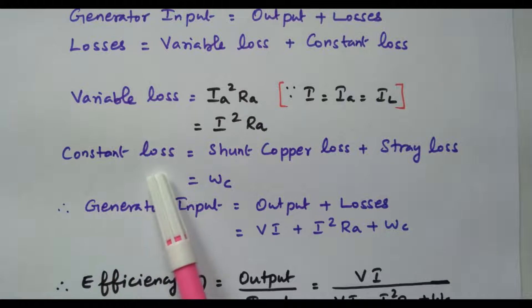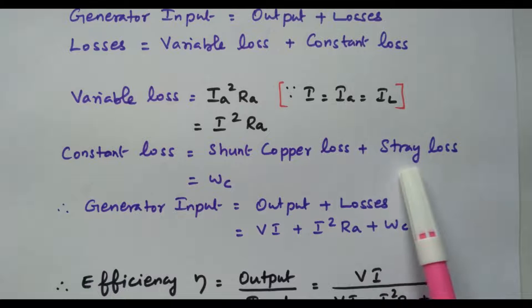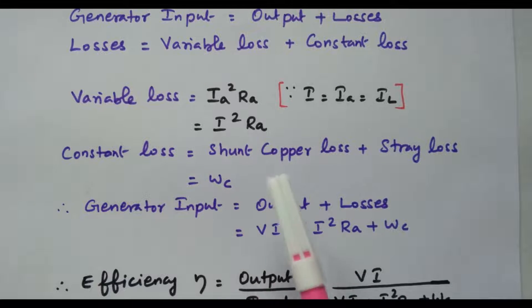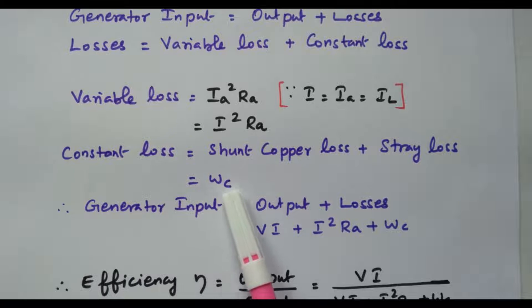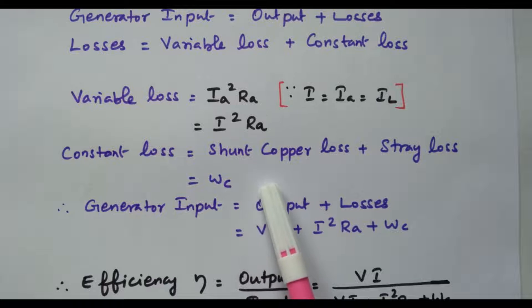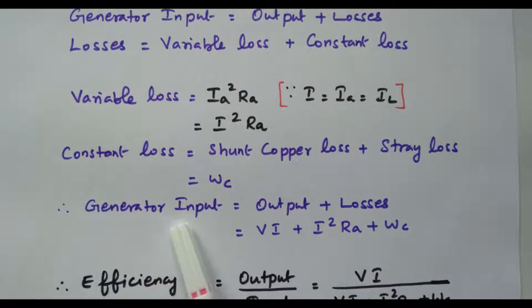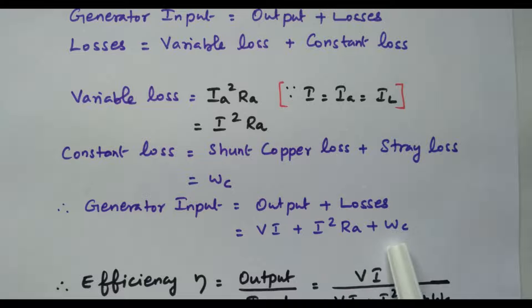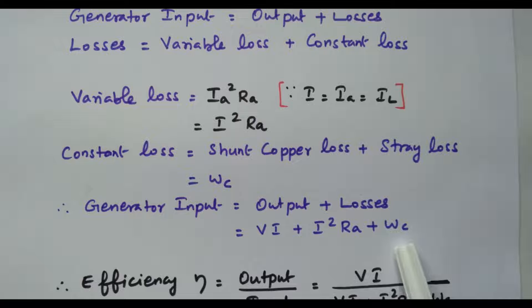The constant loss includes shunt copper loss and stray losses. These do not change with respect to the current, so we denote them as WC. It is always constant and irrespective of the current. So the generator input equals output plus losses: input = VI + I²RA + WC.